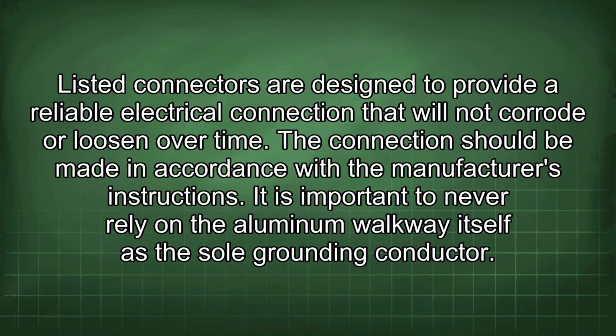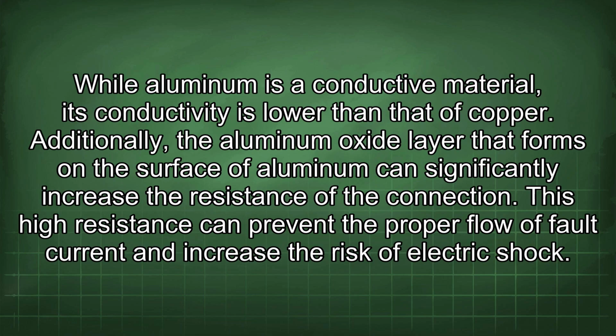It is important to never rely on the aluminum walkway itself as the sole grounding conductor. While aluminum is a conductive material, its conductivity is lower than that of copper. Additionally, the aluminum oxide layer that forms on the surface of aluminum can significantly increase the resistance of the connection. This higher resistance can prevent the proper flow of fault current and increase the risk of electric shock.